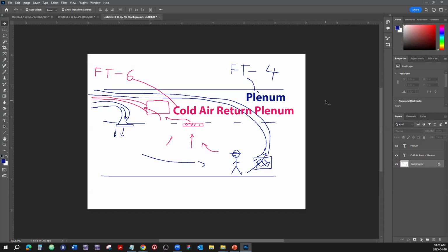Of course, FT4 cable is less expensive than FT6. FT6 is generally about 3 times as much as FT4 cabling. So there would be a temptation, for some people who want to bypass the system, to use the cheaper wire. Don't. All right? You're going to get caught, and it's going to cost you money, if not some sort of legal repercussions as well.